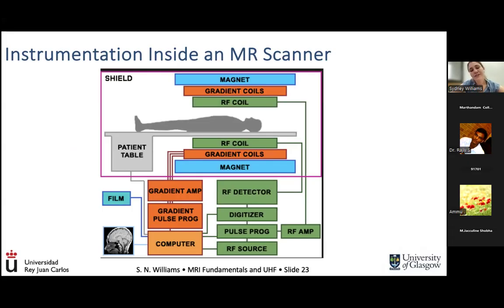If you've seen an MRI scanner, and I had one on the first slide, it looks like a big donut. It can be a bit intimidating, and in fact, it can be claustrophobic for some patients when they go into the MRI scanner, because you're within this big tube, and it's a tight fitting tube. So what is the use of all of that machinery and what are the different components within? Well, usually in most MRI scanners, not necessarily the 7 Tesla scanner that we'll talk about today, you need the radio frequency coil, the RF coil, that's going to create the field that will both excite those atomic nuclei and also receive the signal from them.